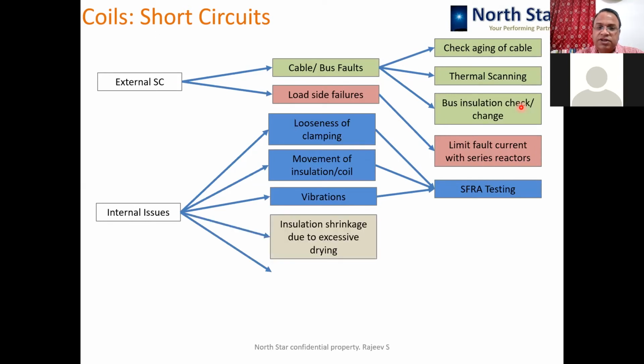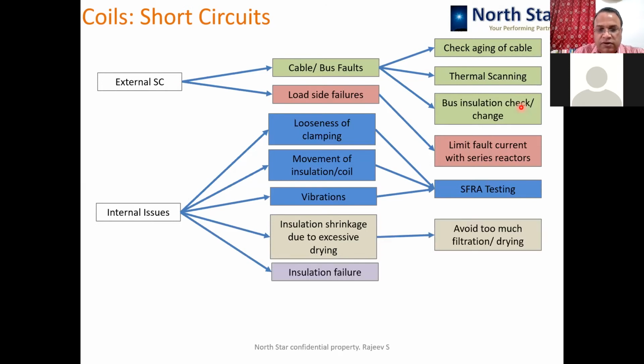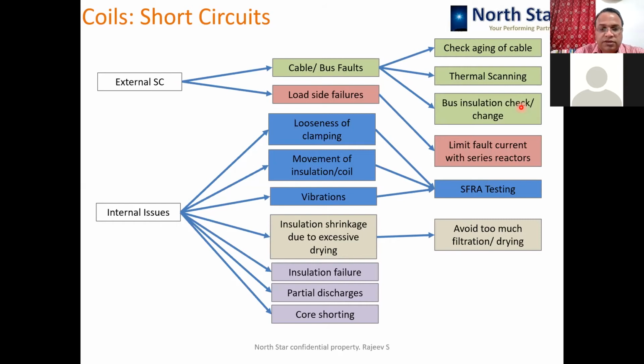Then insulation shrinkage happens due to excessive drying. If the transformer is dried in the factory beyond a limit, then it gets looseness in the winding, and such a transformer can fail at the site. Insulation failure is another reason. Internal partial discharges can cause ultimate damage to the winding conductor, which can lead to a short circuit of the transformer. Then core shorting is another aspect, which causes excessive but slow heating of the winding and decay of the covering of the conductor, which leads to the failure of the coils.